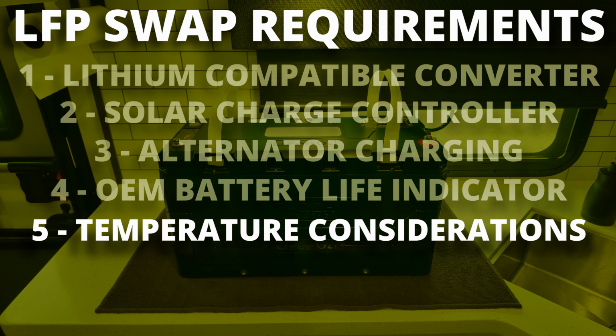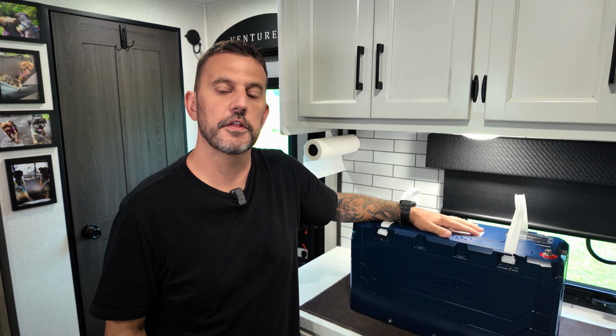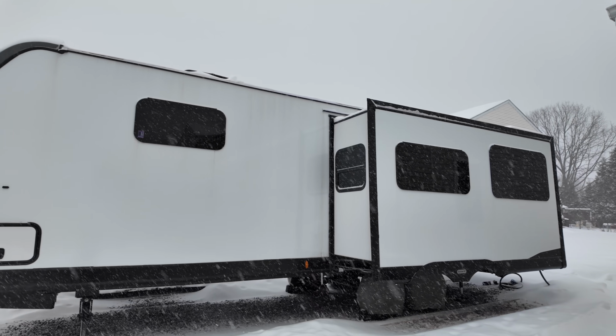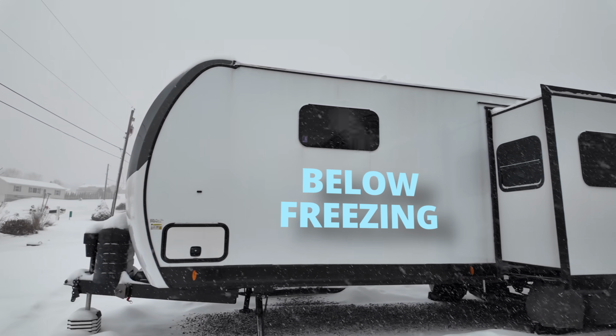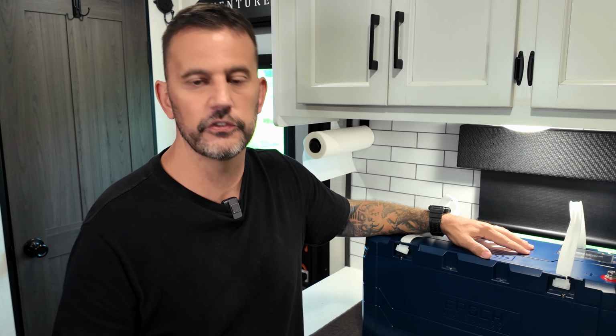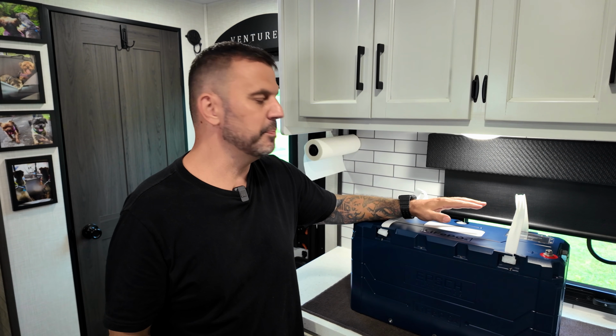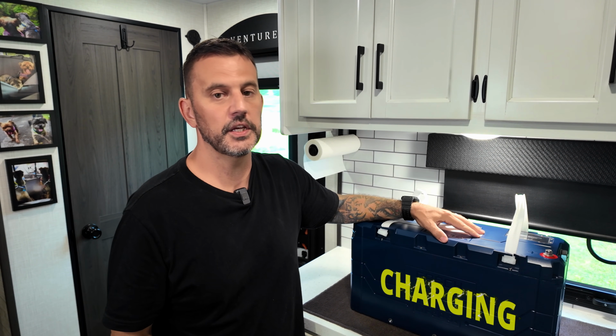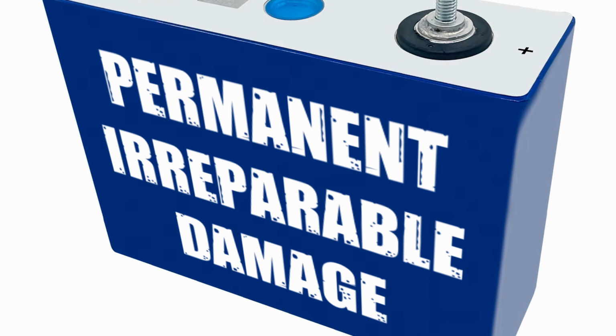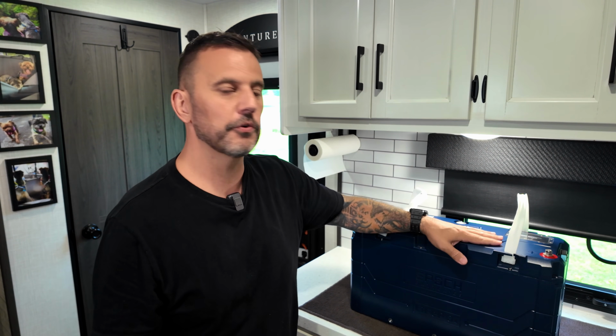Temperature is going to be a factor with lithium. The magic number is 32 degrees Fahrenheit, or 0 degrees Celsius. You can discharge batteries below 32 degrees, and you do lose a little capacity, but the big issue is charging lithium batteries below freezing. It can permanently damage the cells, and it's irreversible.